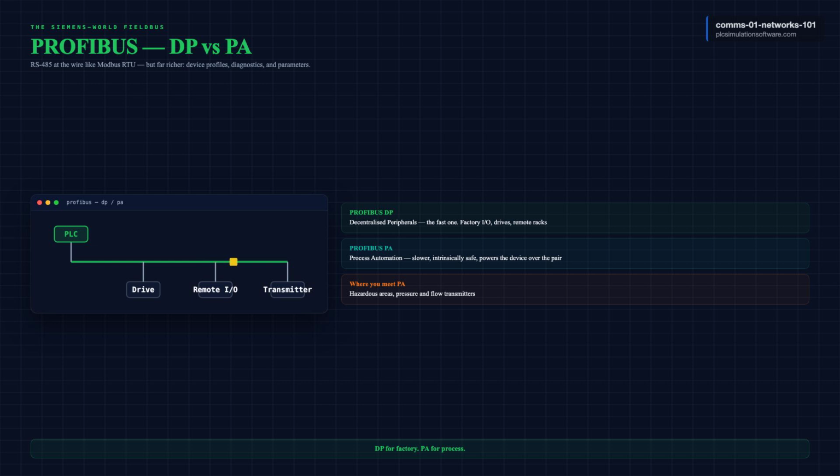PROFIBUS PA is the process one. PA stands for process automation. It is slower, it is intrinsically safe, and it can power the device over the same pair. So you find PA out in hazardous areas, talking to pressure and flow transmitters. DP for factory, PA for process.